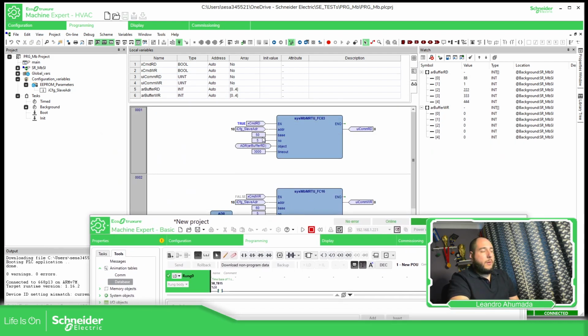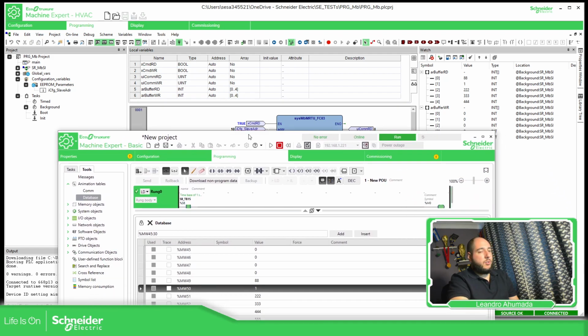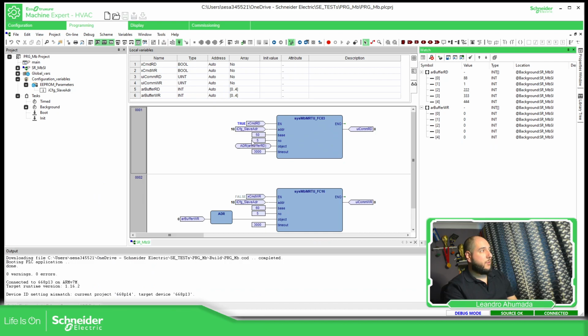Well, on Modbus sometimes it starts base 0, base 1, or you just need to try it here sometimes if you don't read the manual. So sometimes, depending on the systems, if you are trying to point to the MW50, it's the MW50 and there is nothing else to do. Sometimes you just need to subtract one or add one to the register that you want. So in this particular case, if I want to read the MW50, I just need to add one to this.